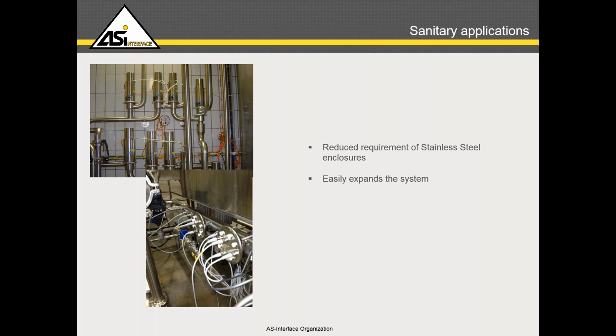Typically people save some I/O points as spares, so whenever they need to add a new valve, sensor, or instrument to the system, it's very easy to add instead of having to pull wire through conduit into that environment.